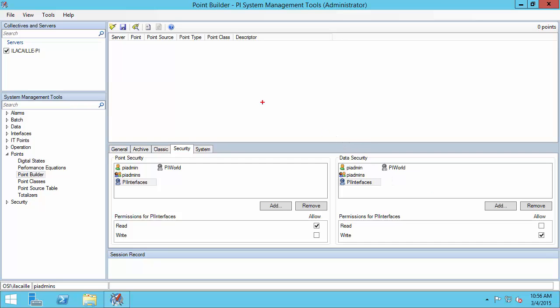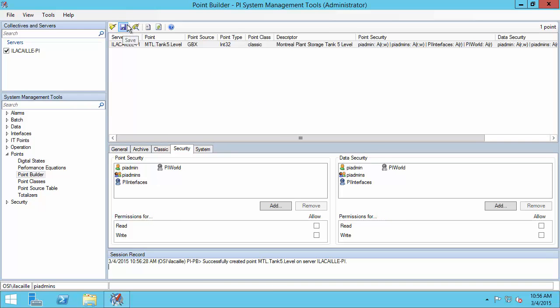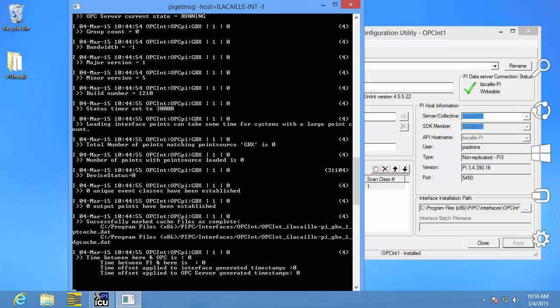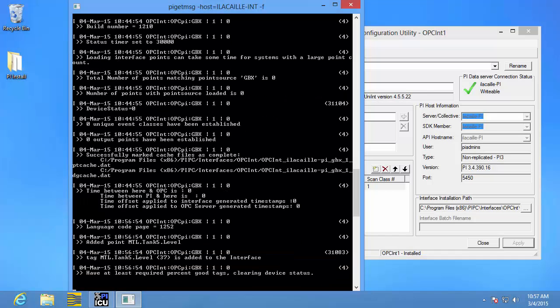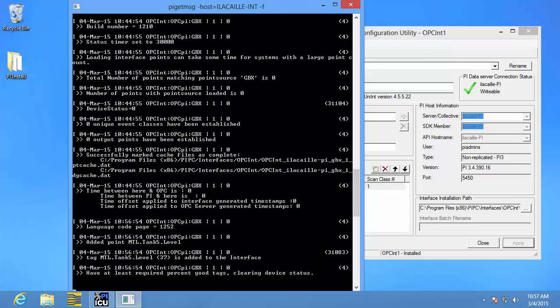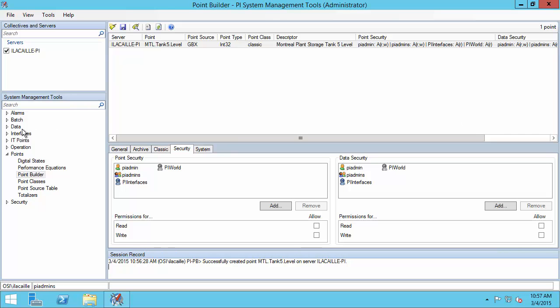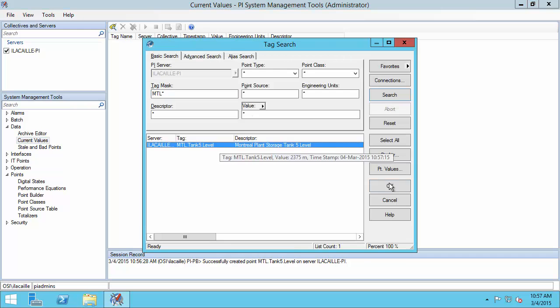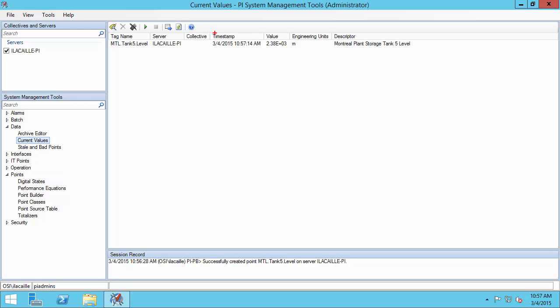That's everything, so now I can go ahead and click save. Now I want to make sure that my PI point is properly picked up by my PI interface instance. I need to go back to my PI interface node and watch my PI message log. Please note that it might take up to 2 minutes for your PI interface to pick up the new PI point from the PI Data Archive. It looks like it picked up my PI point. Let's go back to PI System Management Tools to see if we're getting current data — under Data and Current Values — and we can see that we're getting current data for our PI point.